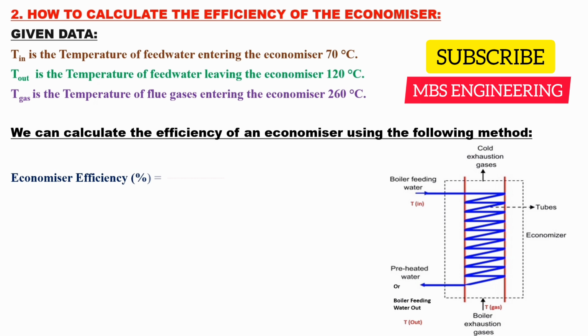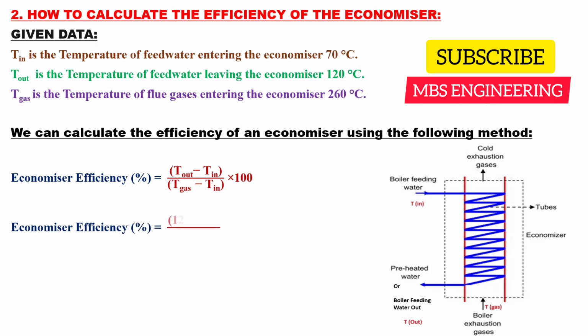The economizer efficiency in percent is equal to the feedwater outlet temperature minus the feedwater inlet temperature, and the obtained value is divided by the entering flue gas temperature minus the feedwater inlet temperature, and then multiplied by 100. The economizer efficiency in percent is equal to 120 minus 70, divided by 260 minus 70, and then the obtained value is multiplied by 100.